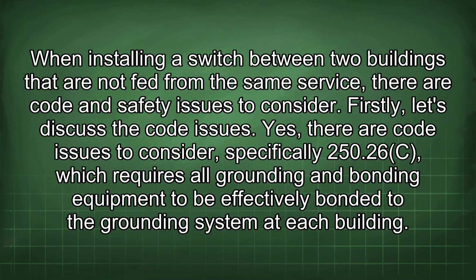When installing a switch between two buildings that are not fed from the same service, there are code and safety issues to consider. Firstly, let's discuss the code issues. Yes, there are code issues to consider, specifically 250.26c, which requires all grounding and bonding equipment to be effectively bonded to the grounding system at each building.